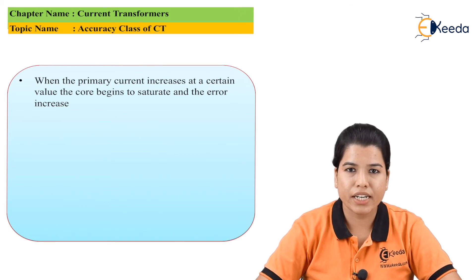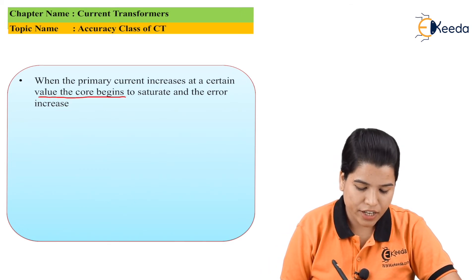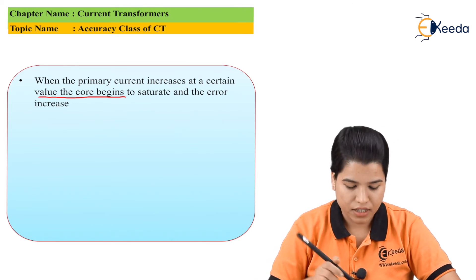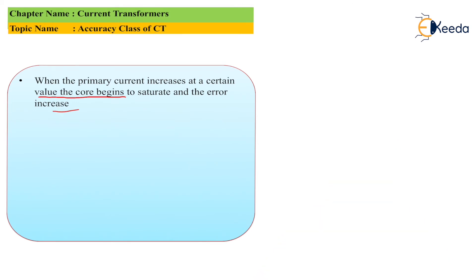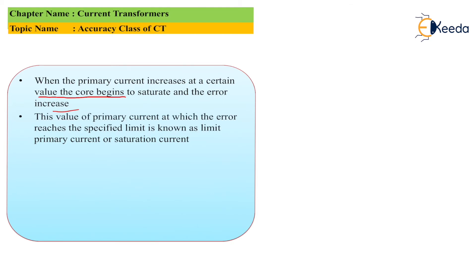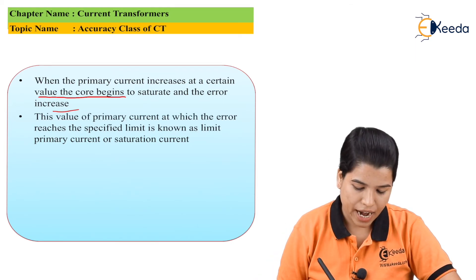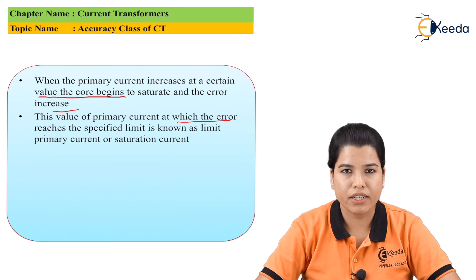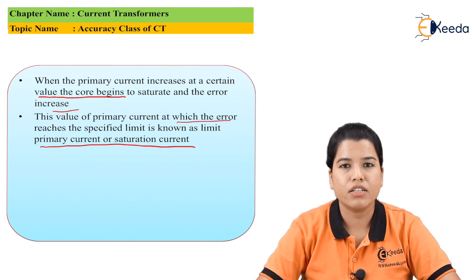When the primary current increases, at a certain value the core begins to saturate and the error will also go on increasing. This value of primary current at which the error reaches a specific limit is known as the limit current or saturation current.